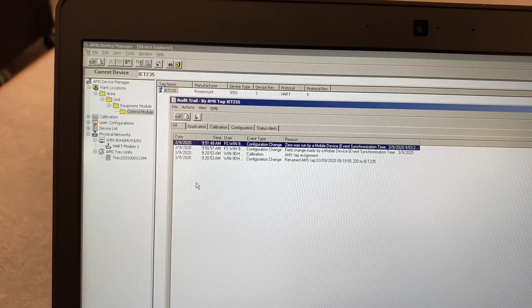So this is a pretty handy tool. We can go out and service equipment that's added to our database here, but it actually isn't physically connected, and we can go around to this equipment, make changes, and it will be recorded in the Trex calibrator, and then when we plug it back in here, it will update. So we could have done like 100 calibrations, and they would all be updated in this database now. It would track the time it was done. So if we want to look back and see when all of our calibrations and stuff were done for our equipment, we would have that all tracked.